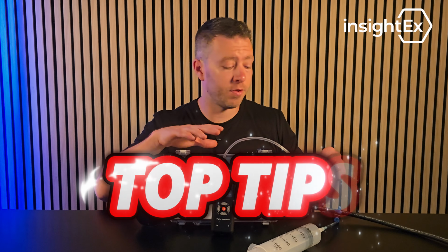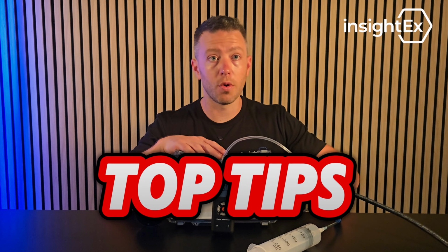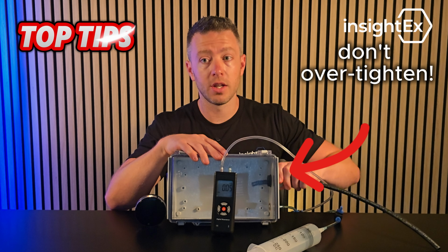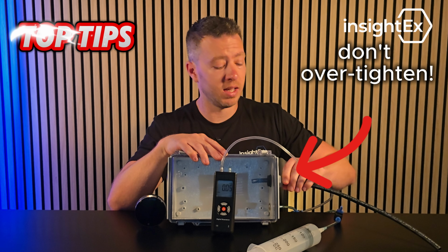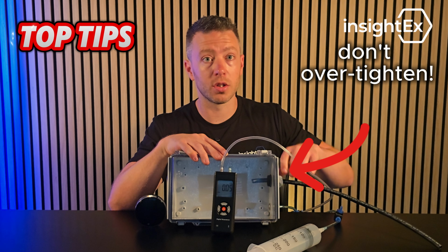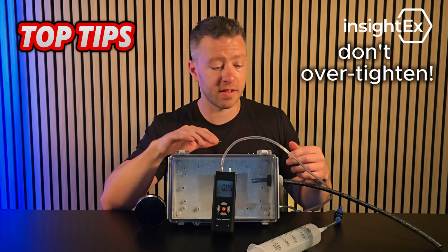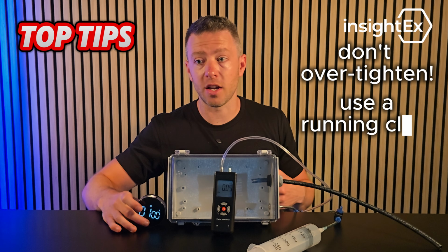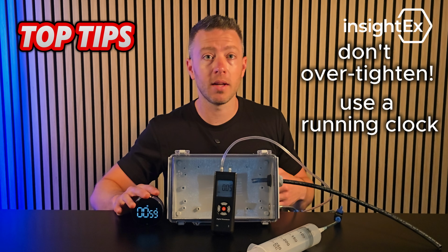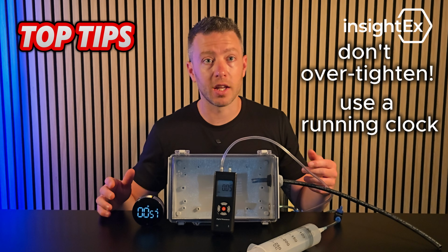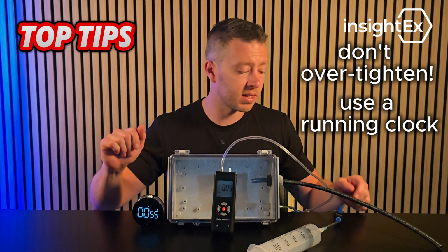Some top tips for performing this test. One, don't over tighten the cable gland. You need just enough pressure to seal. If you over tighten it, you could squeeze the cable and give you a false positive. Two is use a running clock or timer. It gives you a much more accurate result if you're recording the test.